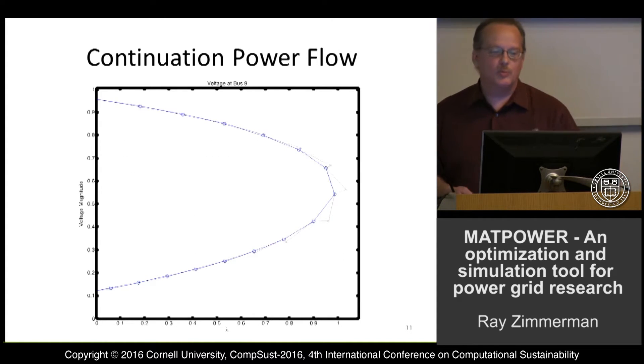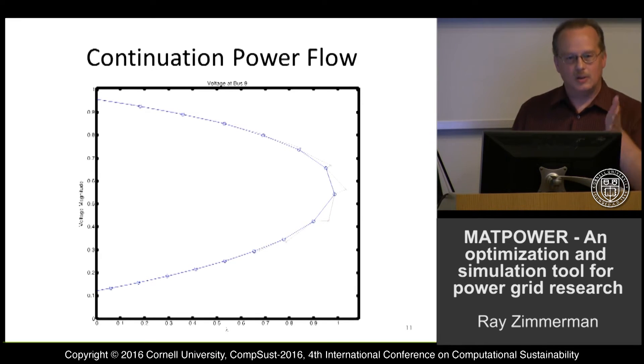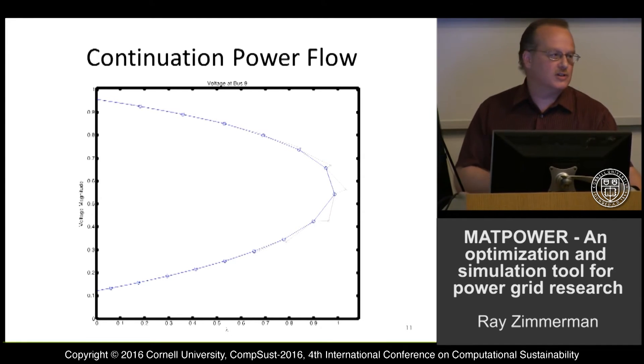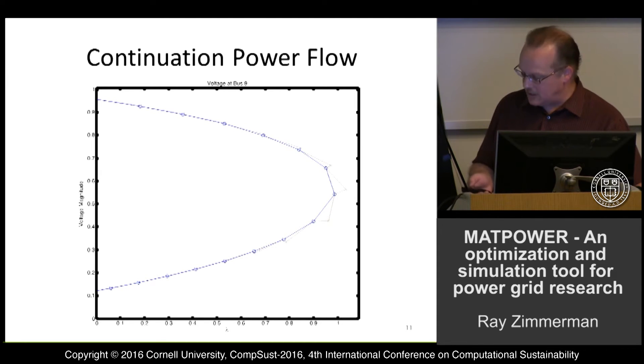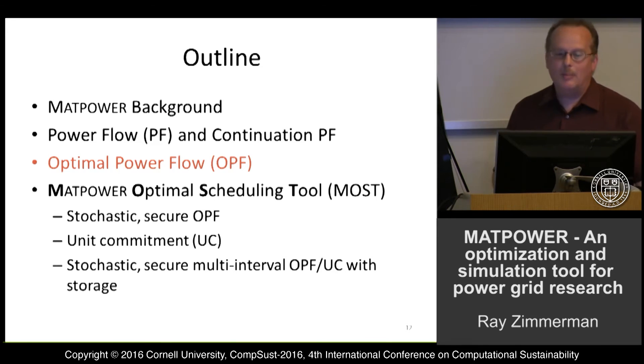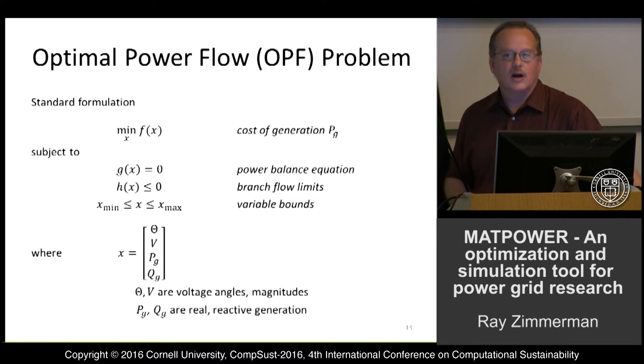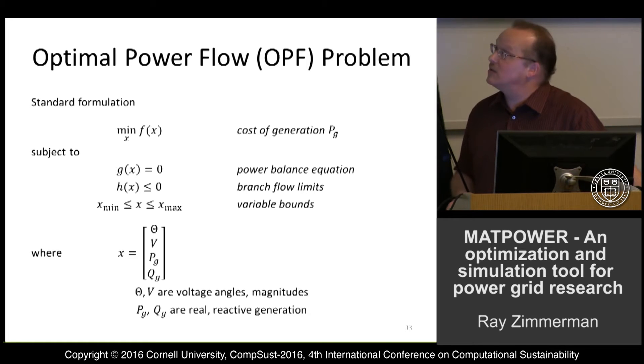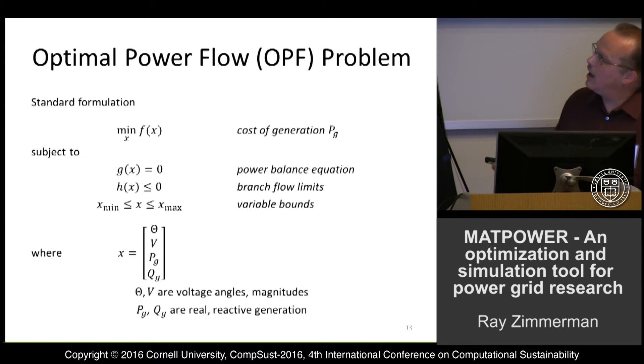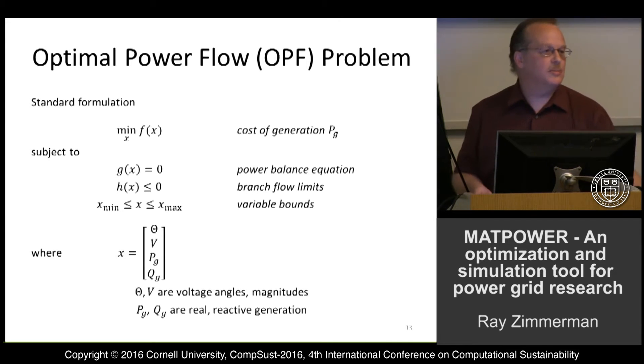The continuation power flow problem is essentially solving a sequence of power flow problems where a given parameter, such as loading in the network, is modified. For example, you might increase loading until you see a voltage collapse — this is the famous nose curve. Optimal power flow, on the other hand, is an optimal scheduling problem with nonlinear constraints: minimizing the cost of generation subject to power balance at each node, constraints on nonlinear branch flows, and bounds on variables such as generation and voltage limits.